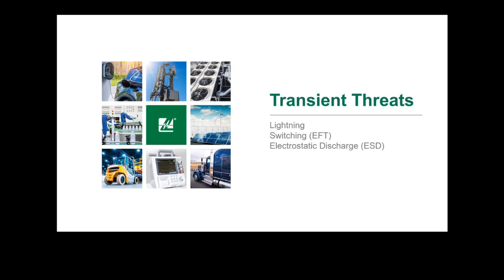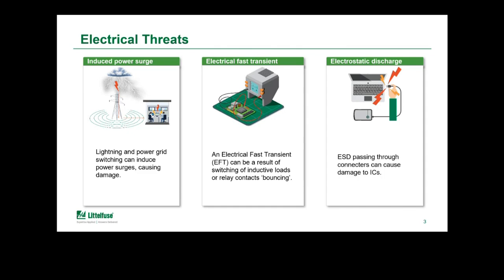But first, we'll talk about the transient threats. About 75% of all equipment failure is due to an electrical overstress caused by a transient event. Semiconductors are more prevalent and increasingly intolerant to transients. Transients can be caused by different atmospheric events. On the very heavy, large energy side, we have lightning strikes. If a piece of equipment is struck by a direct lightning strike, honestly, there's not much you can do at an equipment level to protect it because there's just too much energy to handle. What we really try to prevent damage from is induced lightning strikes or proximity strikes. These can occur several miles away, but can induce a transient into the cabling, whether above ground or below ground, and then transmit that transient energy down the cable to the end equipment. This type of event can be in the thousands, in some cases even tens of thousands, of amps that need to be handled.